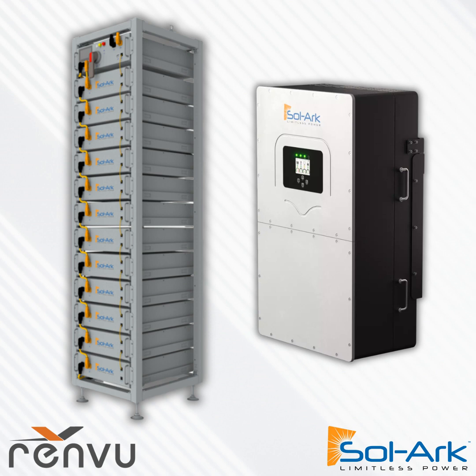Is AC coupling of the battery with zero export difficult or impossible? It's not impossible if you implement a load sink—whenever you start exporting to the grid, turn on a large enough load that you won't export. So AC coupling with zero export isn't necessarily impossible, although if the inspector says they need it to be impossible even without a load sink, that strategy won't work. The fundamental difficulty with AC coupling and zero export is that you use frequency shifting to turn off the inverter, and if the grid is online, you can't frequency shift it since it's the stronger source. So you need a more advanced control scheme to disable grid export with AC coupling.